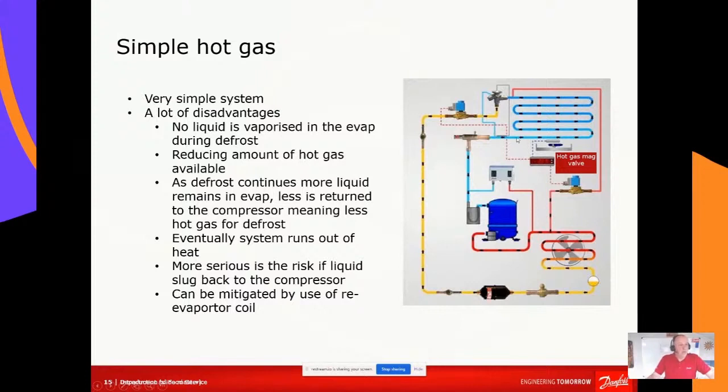Then we've got a crankcase pressure regulator valve or might be an evaporator pressure regulator valve, and that's the normal operation. If you want to do something very simple, you can take a tapping off the discharge line through a hot gas mag valve or solenoid valve that basically feeds hot gas into your expansion line just after the expansion device.